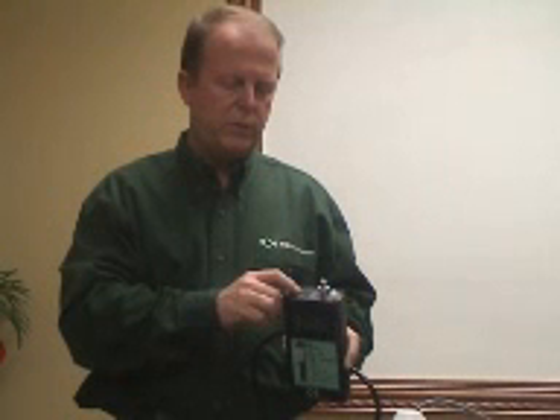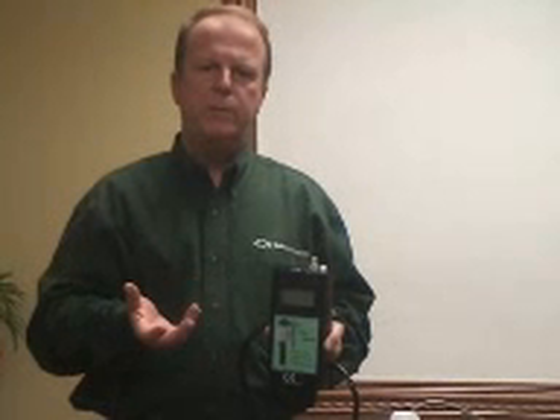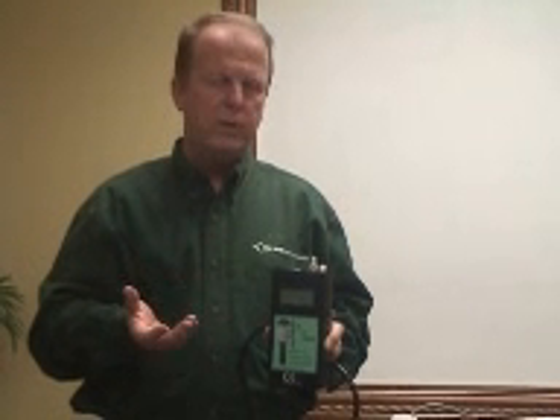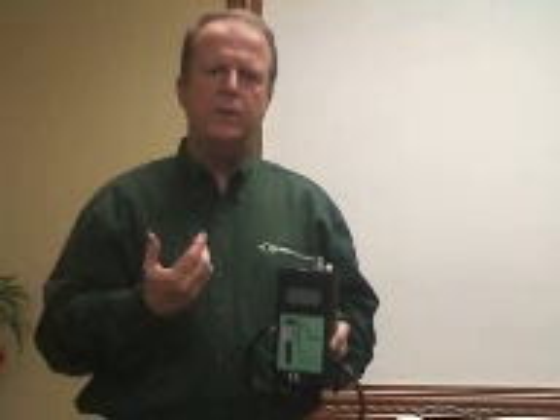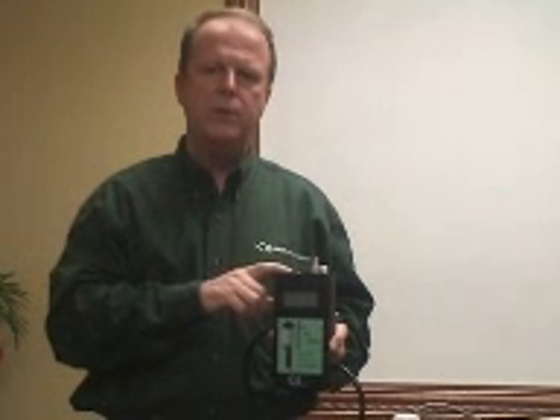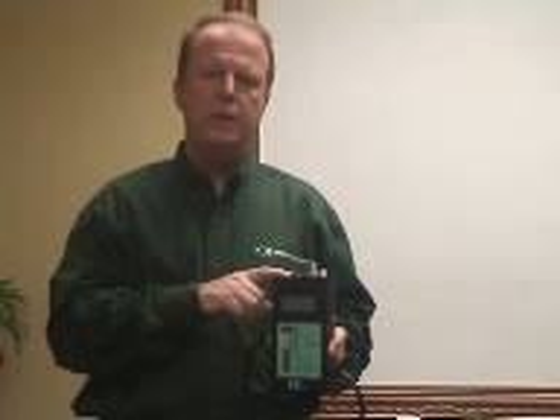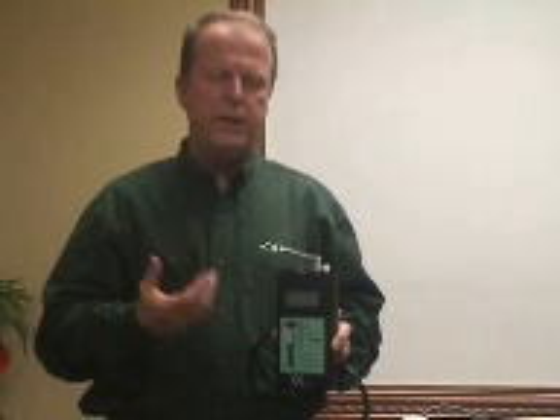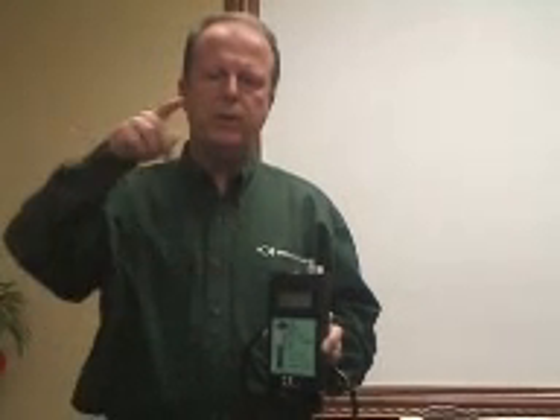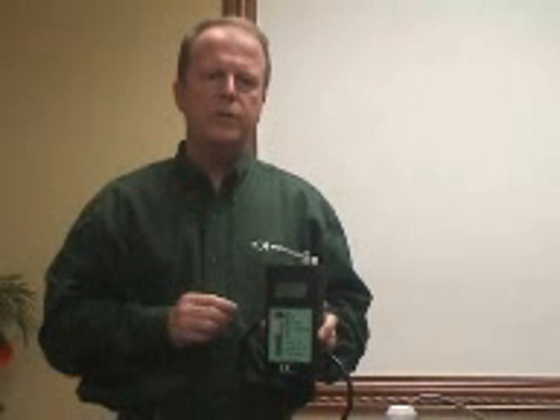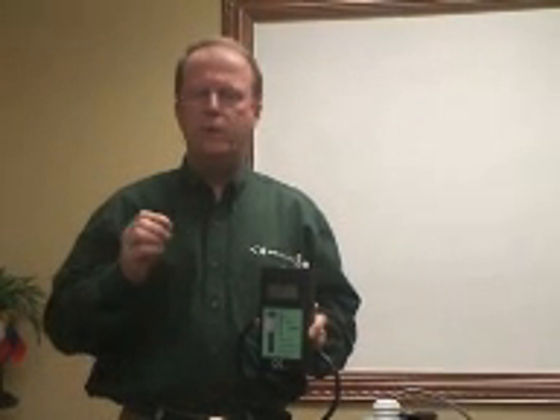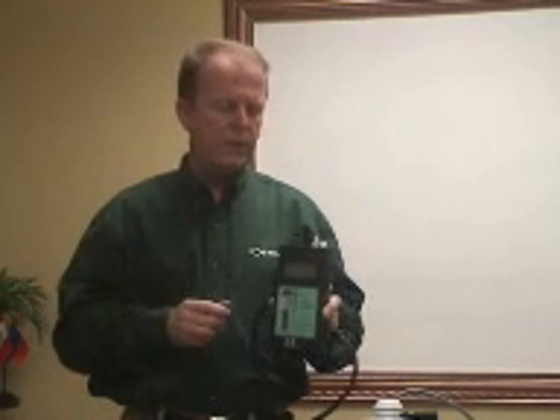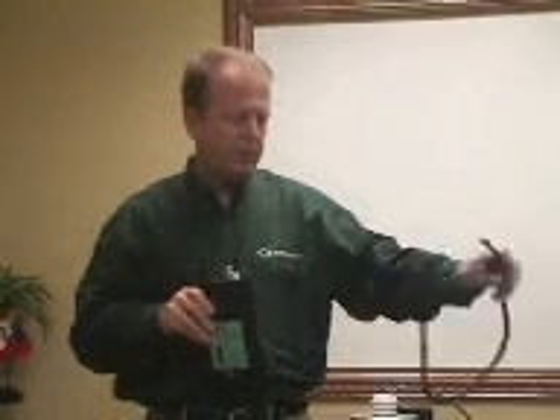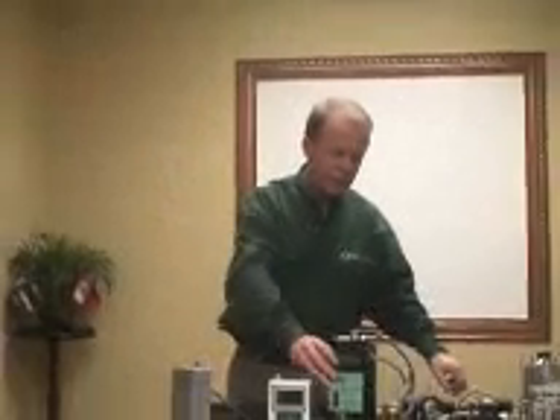The RS-232 can be connected to your laptop or a Palm Top. BGI supplies freeware, free software, with which you can collect the instantaneous flow rate, temperature and pressure data that this calibrator is recording. It goes into an ASCII file. That ASCII file can be looked at as a table, or you can generate a single-page printed report that you can use as a calibration certificate at the end of your sampling event.